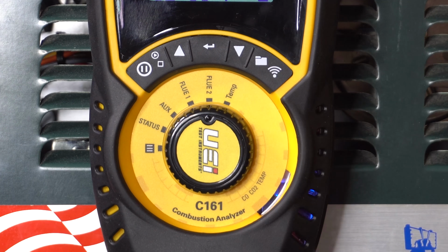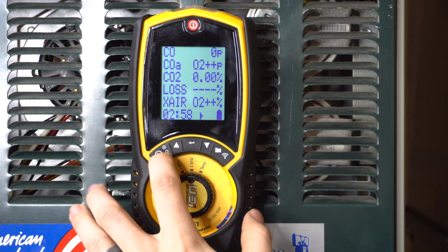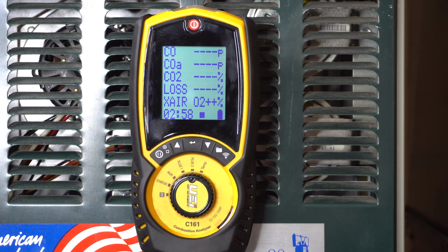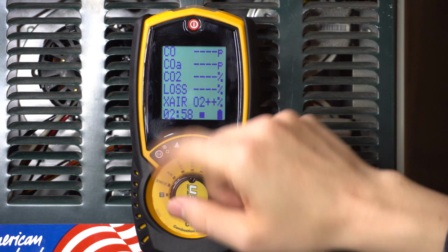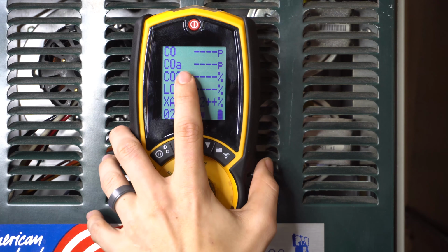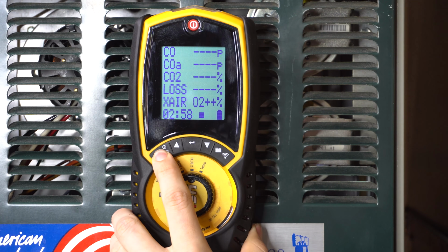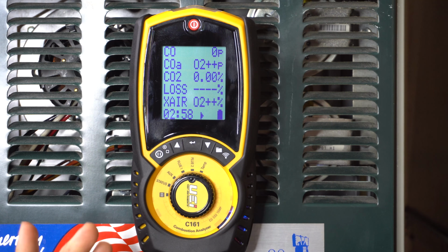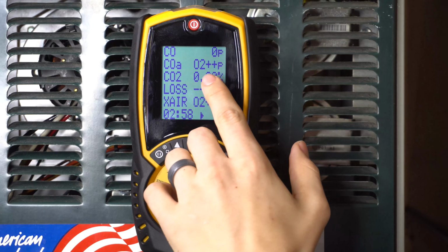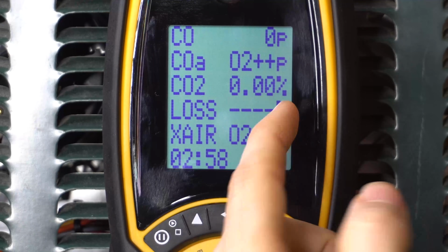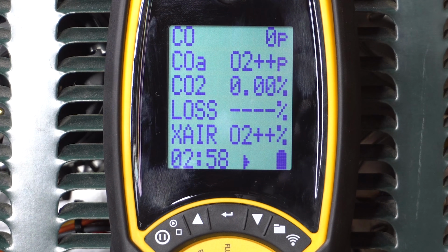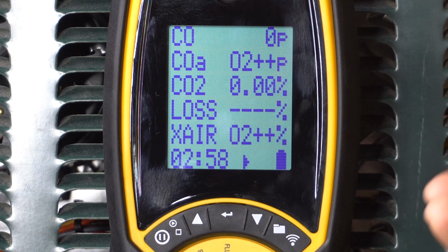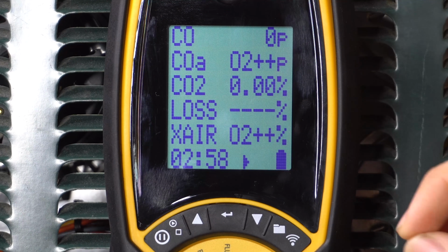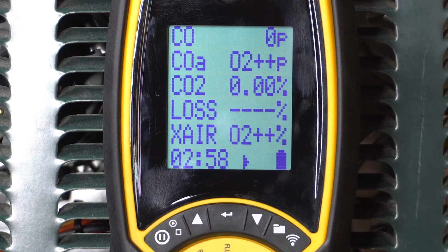Our next one is Flue 2, and the reason they're separated is because they have different readouts. Pause it again. Our second screen has CO for carbon monoxide, COA, and I'm not quite sure what the A stands for. If you resume it, if I had to guess, COA just means that if the analyzer is reading over 200 parts per million carbon monoxide, an audible alarm will sound or the meter will start to beep to notify you that the carbon monoxide levels are getting high.